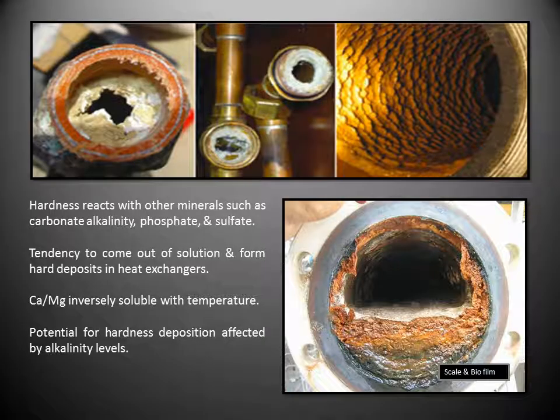Within the protected slime layer, microorganisms can cause speedy corrosion, causing the walls of cooling towers and heat exchange systems to become corroded. The biofilm prevents materials meant for corrosion protection from reaching the surface. Furthermore, microbiological reactions can accelerate corrosion reactions, and microbial products can corrode materials. Biofilm creates an isolation layer on heat exchange systems, causing them to no longer function properly.